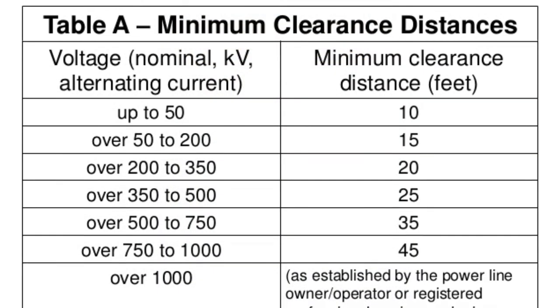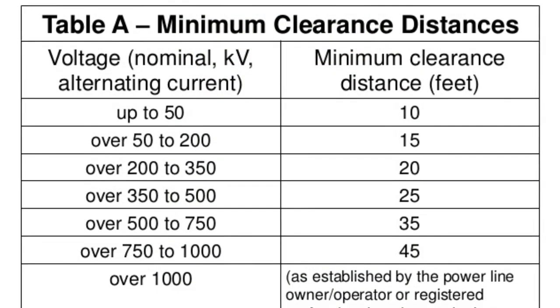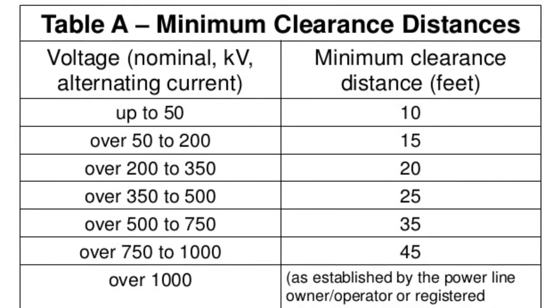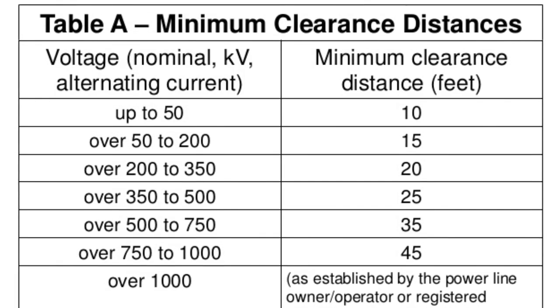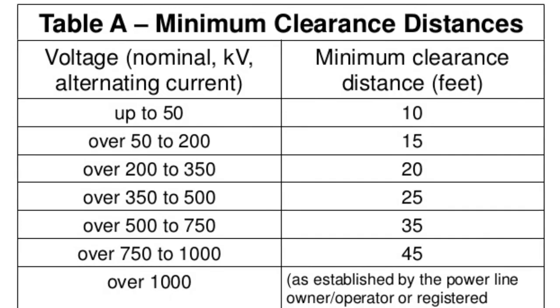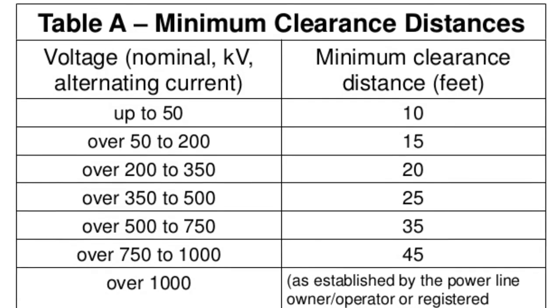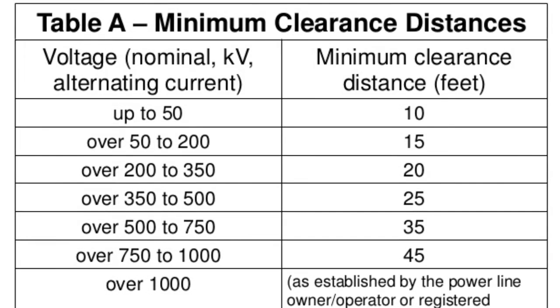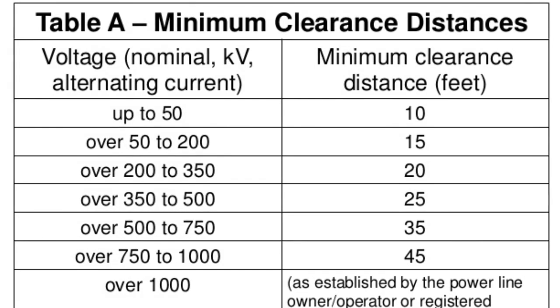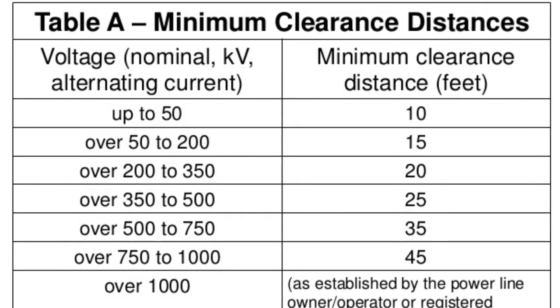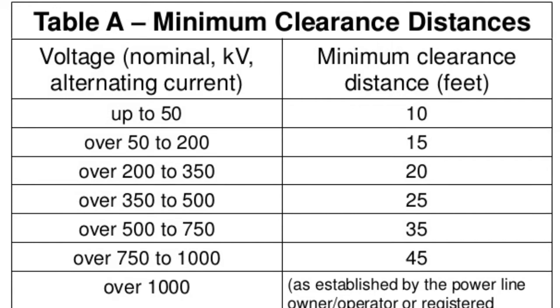If you are working under unguarded energized overhead lines, the clearance distance is 10 feet for voltages of 50 kilovolts or less. The clearance distance is 10 feet plus 4 inches for every 10 kilovolts greater than 50 kilovolts. An easier way to remember this is add 5 feet for every 150 kilovolts over 50 kilovolts.